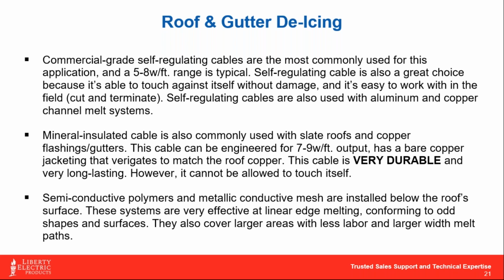If we're going to use that same type of cable on an EPDM roof, we might want to get that down around 7 watts a foot, just to ensure we don't have enough heat output to worry about it embedding itself in the surface of the roof. MI cable is a very durable product. It's not the easiest to work with, but once you put it up on a roof, it's pretty much one and done.